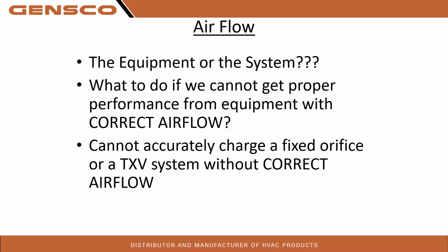Everybody knows that our gas furnaces come preset from the factory at 350 CFM per ton. So that's the S9V2, the S8V2. We have to adjust the gas furnace to 400 CFM per ton and then put the system in check charge heating or charge mode cooling. Once we achieve a good 10-degree subcooling in cooling, or we get pretty close to the pressure curves in heating during heating season, then we can start dialing in and bumping up that airflow if we have a longer heat run, or if they have humidity issues, we can tone down that airflow. Airflow noise, we can tone down the system too. But once we confirm that we have a good refrigerant charge with 400 CFM per ton, then we can start playing with the airflow. And hopefully the ductwork is designed correctly, which static pressures will show that data.